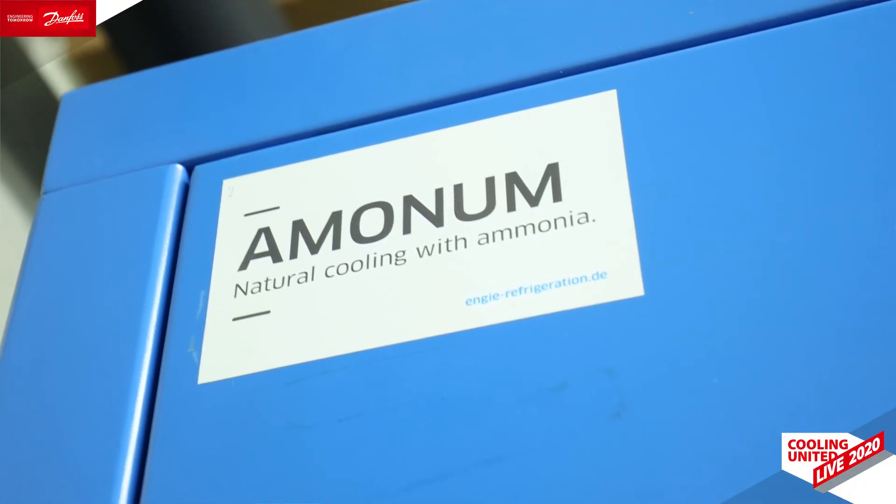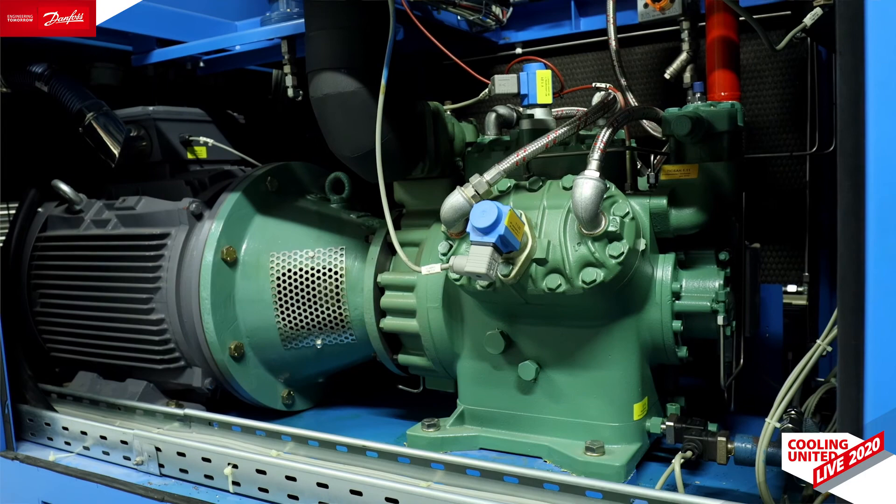Welcome back — now in the machinery room of Engie Refrigeration. In the background you see two ammonia heat pumps. These devices supply our headquarters with heat by using the natural refrigerant ammonia. Here, geothermal energy is used as a heat source and transferred to higher temperatures via the heat pumps, to the storage tank and the underfloor heating. Each heat pump contains a piston compressor driven by a frequency-controlled motor and can provide up to 170 kilowatt of heat at a temperature level of 45 degrees. The ammonia filling quantity is optimized to less than 10 kilograms, minimizing demands on engine room equipment. In addition, the enclosure acts as sound insulation.